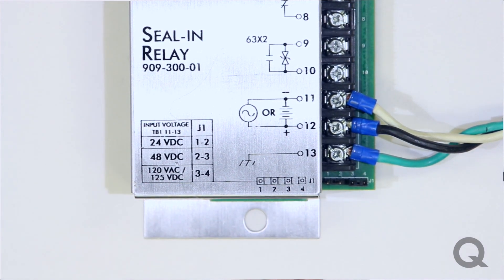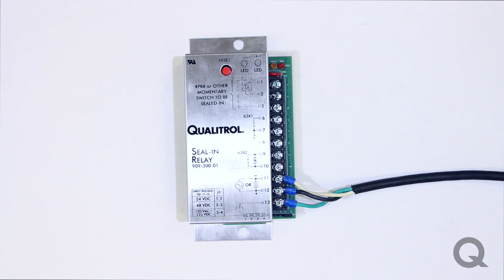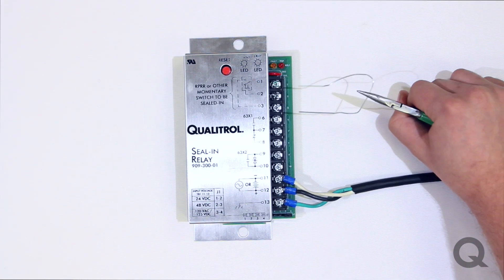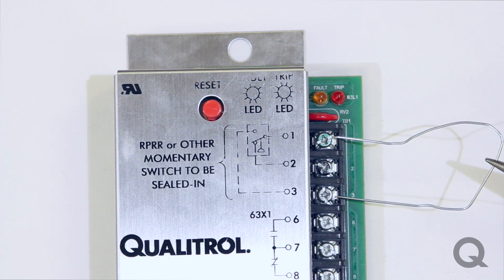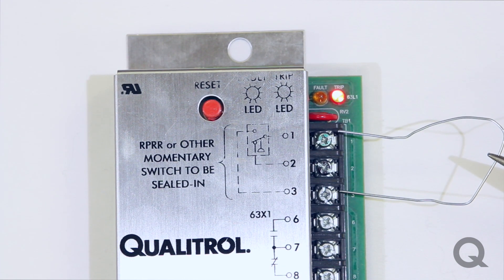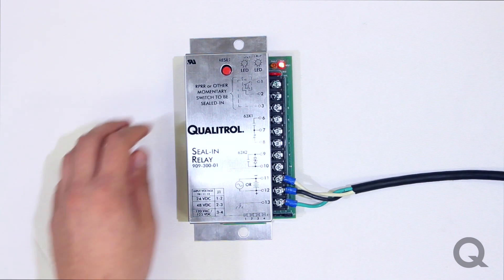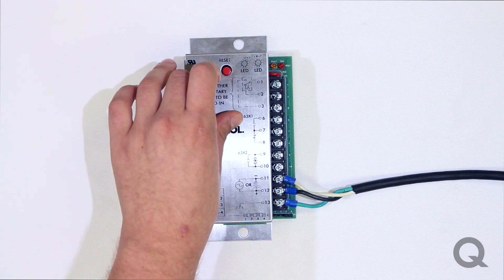I have this unit hooked up and I'm going to show you how to test the Seal-In Relay. I'm going to simulate a rapid pressure increase by creating a jumper between pins 1 and pins 3 on the Seal-In Relay. When this happens, you will see the red LED fault light trip. That means a rapid pressure rise has been detected, the Seal-In Relay has been activated, and all of these contacts have switched. To reset, press the red reset button and this will clear the fault.